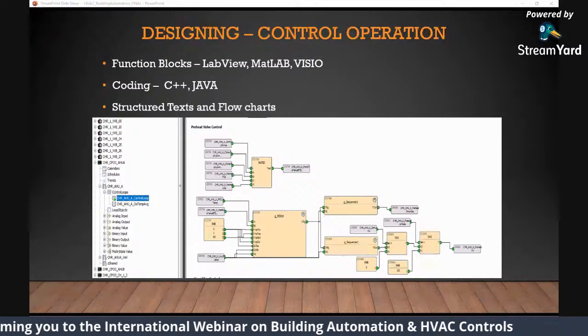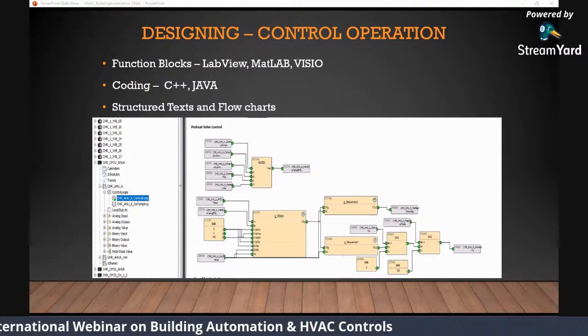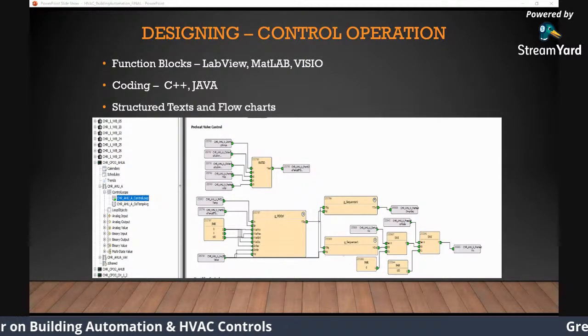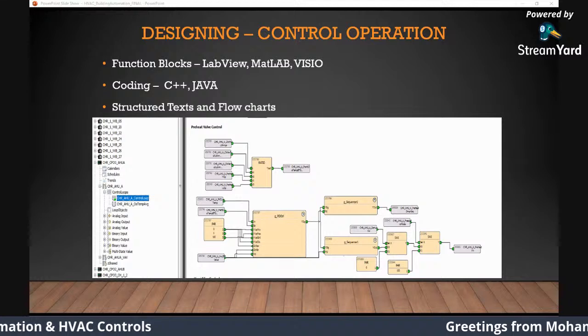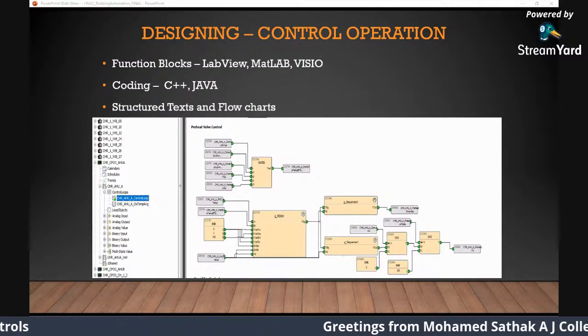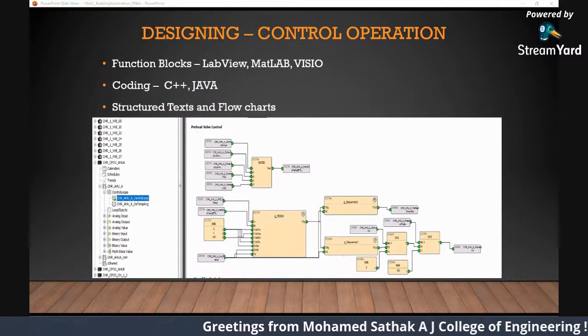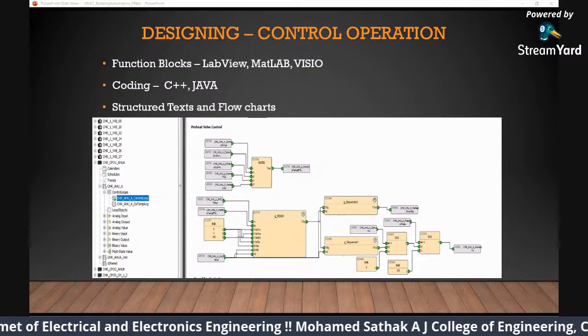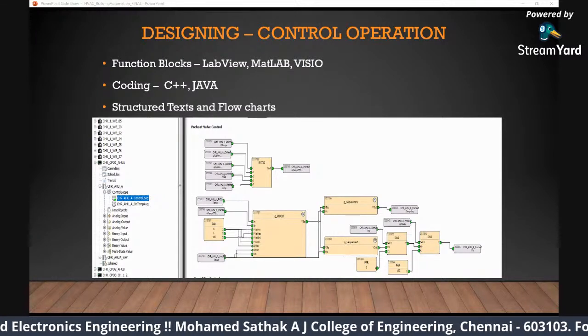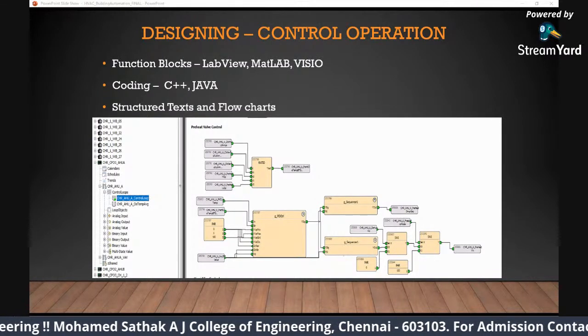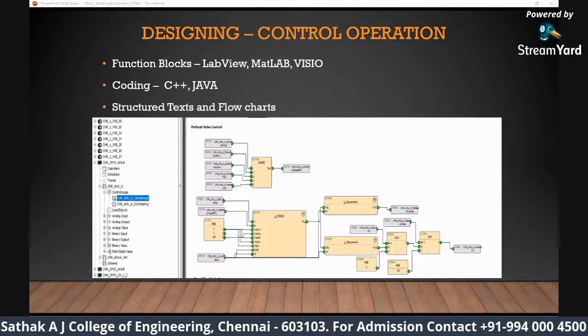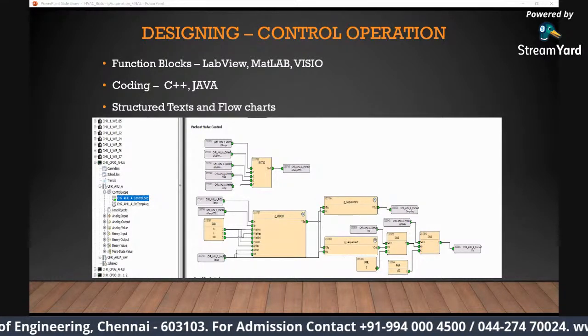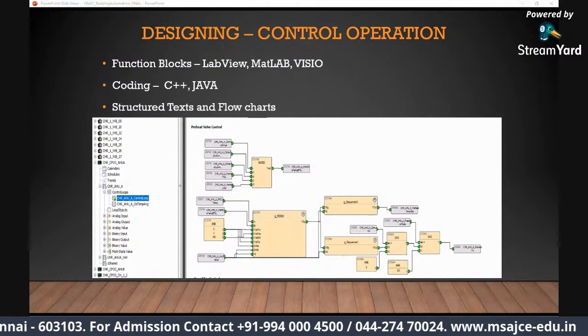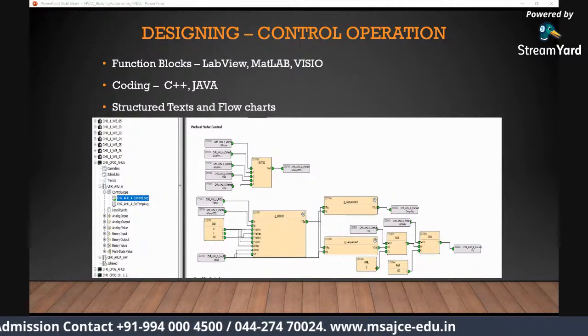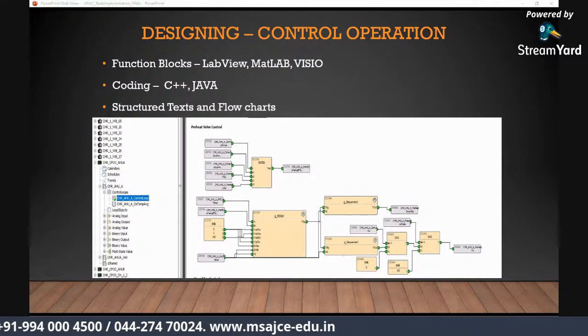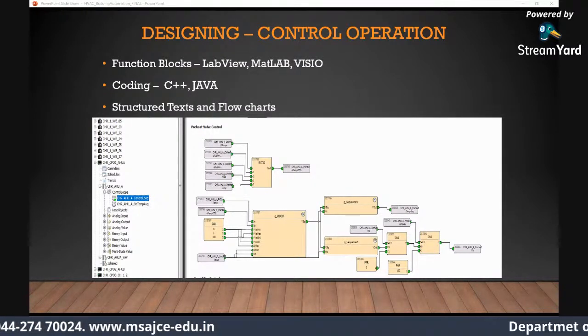Let's say it's a conference room and there are two split units. Let's say there is an occupancy sensor in the room. If there are no people in the room, your controller will measure the occupancy sensor, and it will automatically diminish the intensity of the light in the room. Let's say if there are five people, it will increase the intensity of the light, and accordingly it will increase the split air units. If there are more than 10 people, it will turn on your second split air unit. We'll call it duty standby.